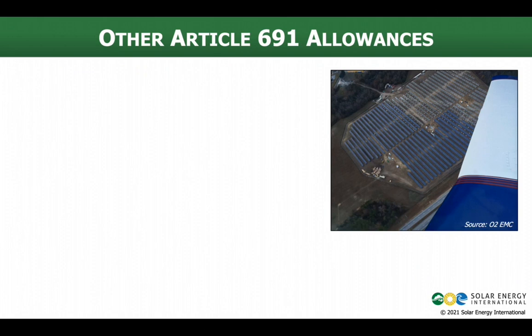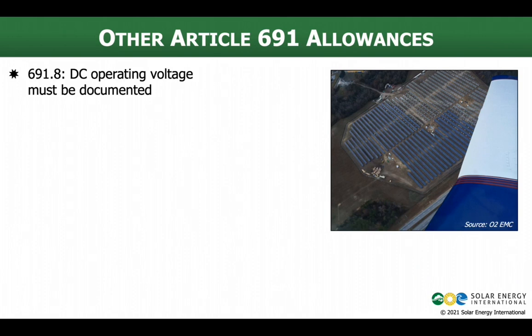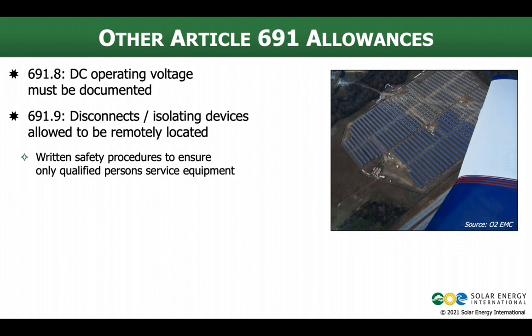So some of the allowances in Article 691 include things like DC operating voltage. It has to be documented, but we have the capability to do things like modeling the system to determine what that voltage may be, allowing us to potentially get more modules in a source circuit. More power per source circuit drives down system cost.